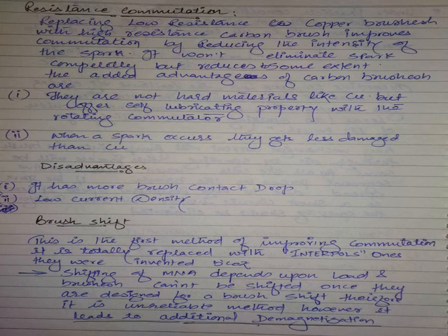As the armature current further increases, what happens to cross-magnetization? Increases. As the armature current further increases, the armature flux is increasing, so more cross-magnetization. So the shifting of MNA or theta is directly proportional to load current. That's all. Shifting of MNA or theta is not a fixed value. Theta means this MNA, which shifts in the direction of rotation of the generator, depends significantly on load.